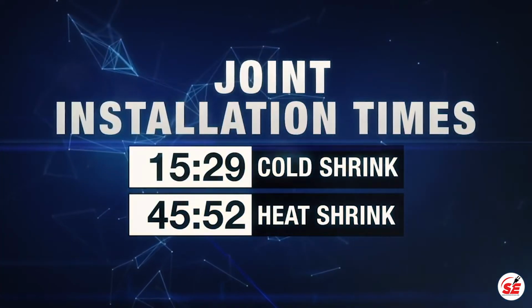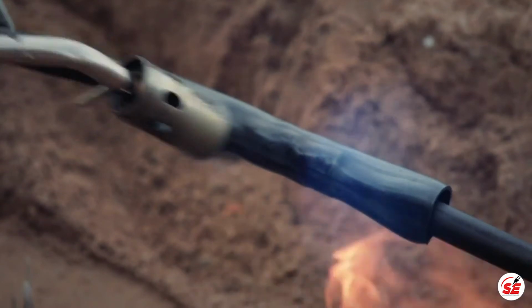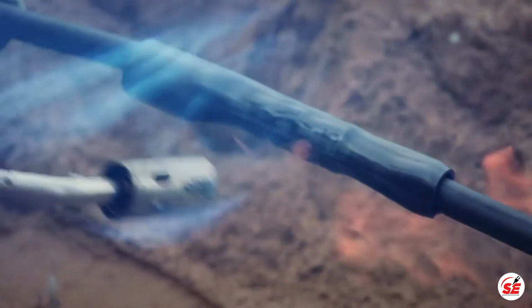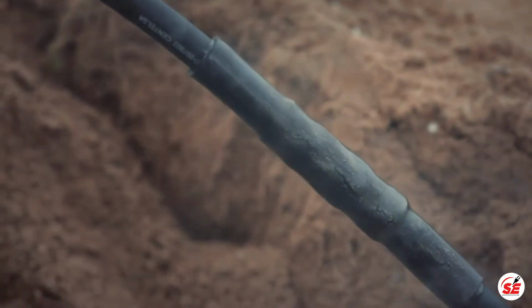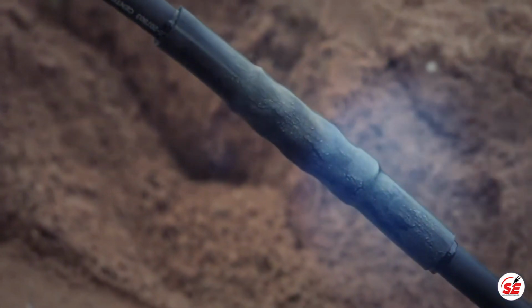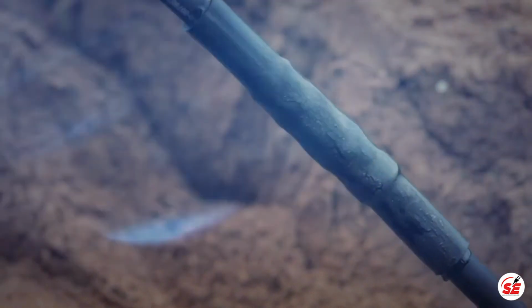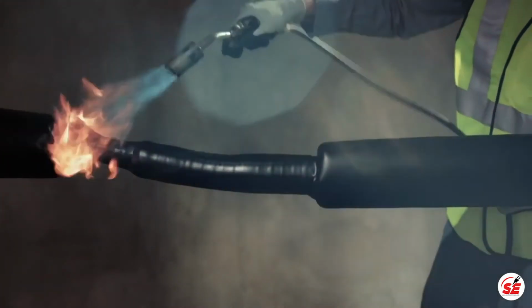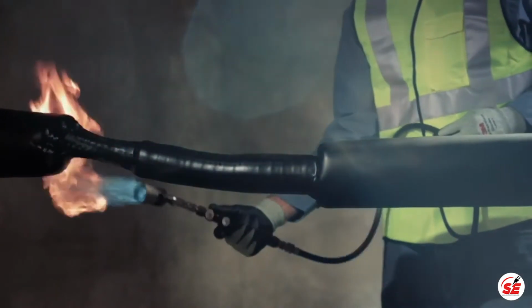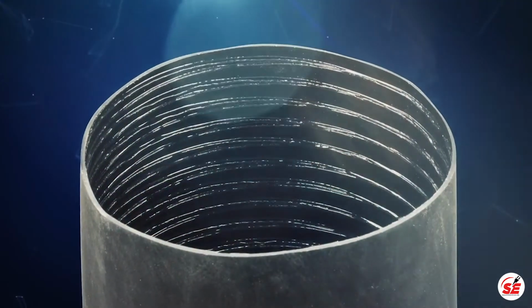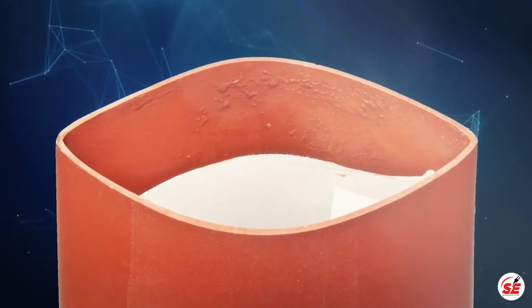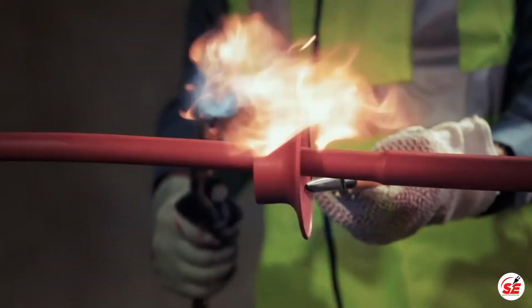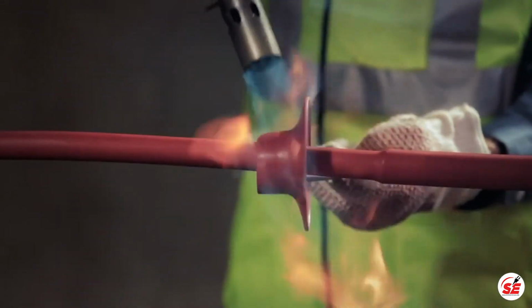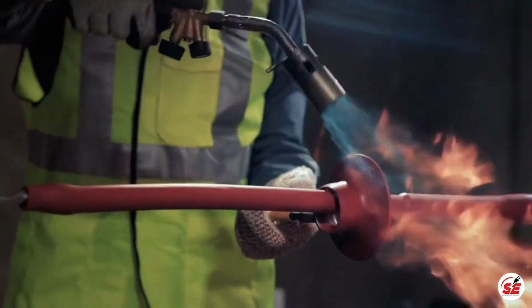However, with heat shrink, a heat source needs to be applied consistently all around the tube. Inconsistent application can result in thinner insulation or voids in the insulation, which will result in partial discharge and ultimately electrical failure. Since there is no constant inward pressure with heat shrink, adhesives are used to environmentally seal, and installers have to heat the tubes until these adhesives ooze out. Moreover, if a heat shrink outdoor termination is being installed, the installer still has the added step of attaching each skirt individually.